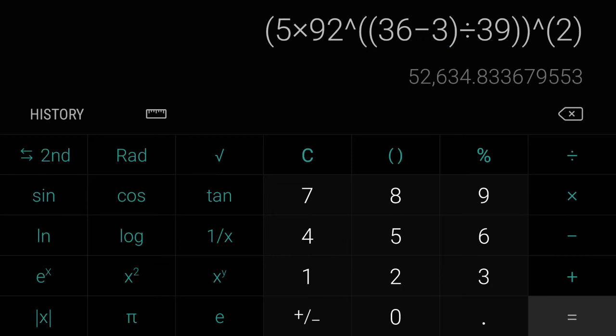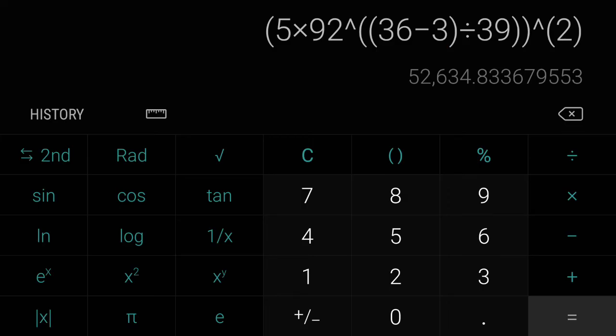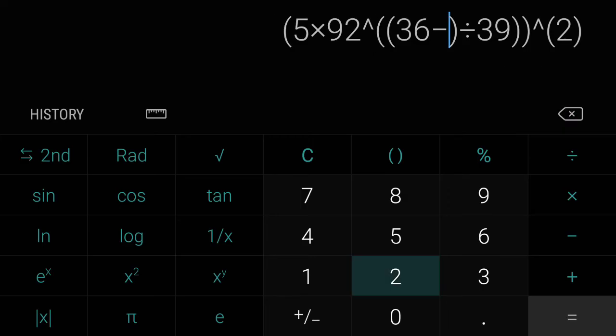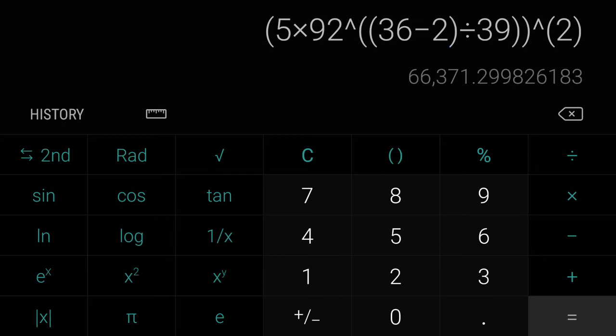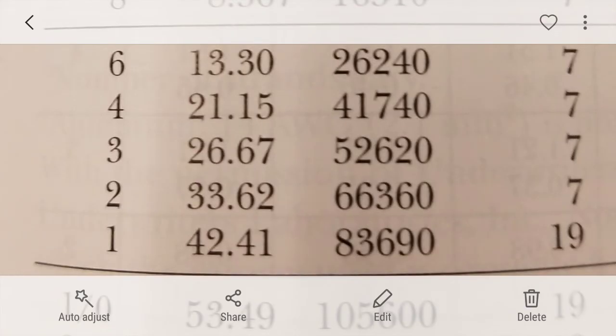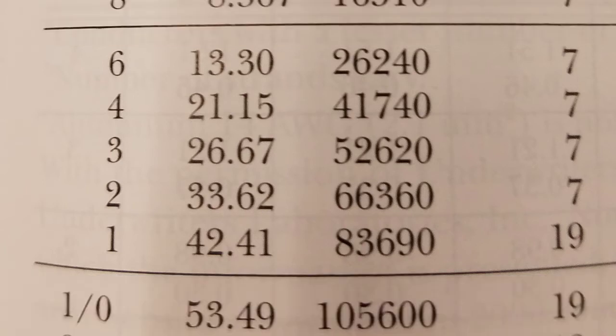So if you follow what they've done here, I don't know if that's a mistake or if there's a proper reason for it, but let's check 2 gauge. 66,370 if you round properly. So they did it again, 66,360, they round down a whole tenth, or actually eleven places, eleven points, whatever.